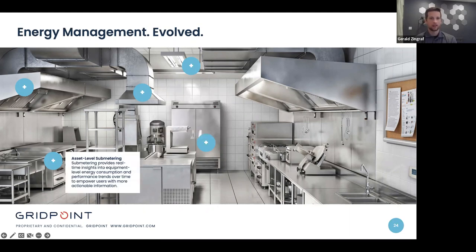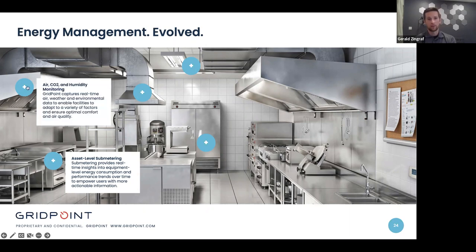If you look over on the left-hand side, we've got submetering that just provides more data for our reporting, our analytics, our benchmarking, our testing, et cetera. And then at the top left, we also have sensor data that we can throw in as well. So temperature and CO2, humidity. This isn't just for the reporting and finding anomalies. It's also, I mentioned, for this smart feedback loop. If you have humidity issues, and you're trying to squeeze a little bit of relative humidity out of your space, that humidity sensor can talk to your HVAC unit and have it run the stage one compressor to drop humidity a little bit. Same thing with CO2. We could have a CO2 sensor that talks to your HVAC unit, to your thermostat, and tells us to bring in some fresh air to kind of swap out the air there.